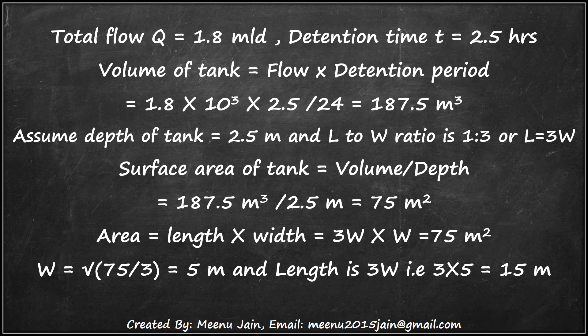Assumptions: depth of tank is 2.5 meters and length to width ratio is 1 to 3, so length will be 3 times the width. Thus surface area of tank is volume divided by depth, that is 187.5 cubic meters divided by 2.5 meters, which equals 75 square meters.